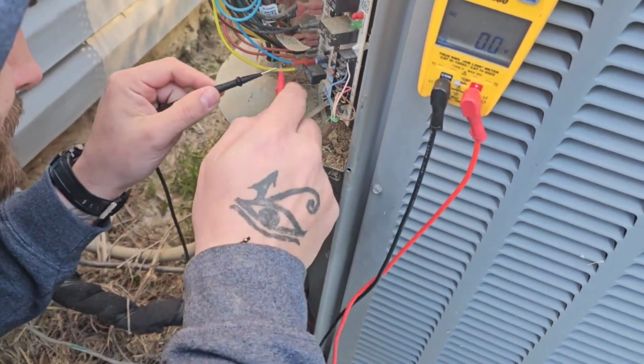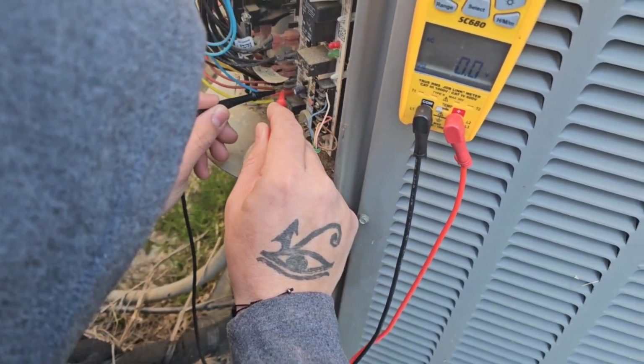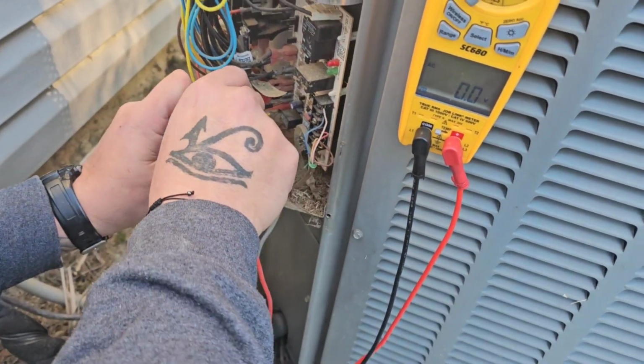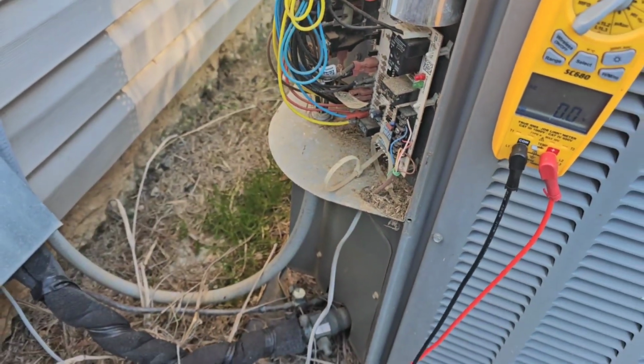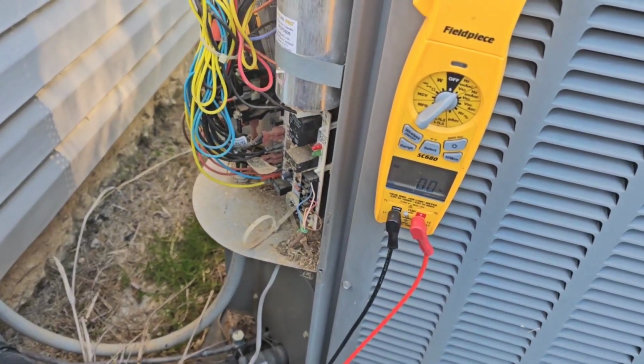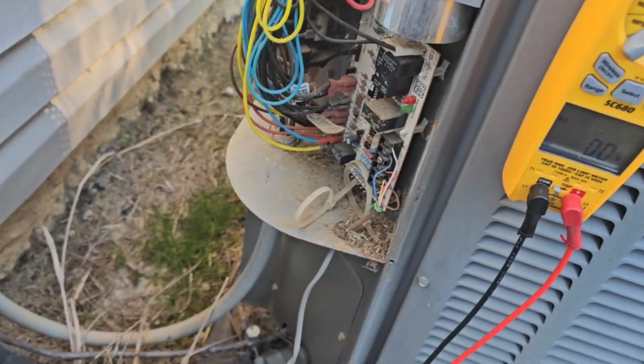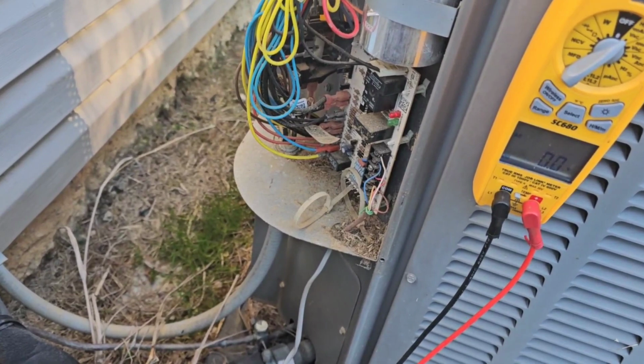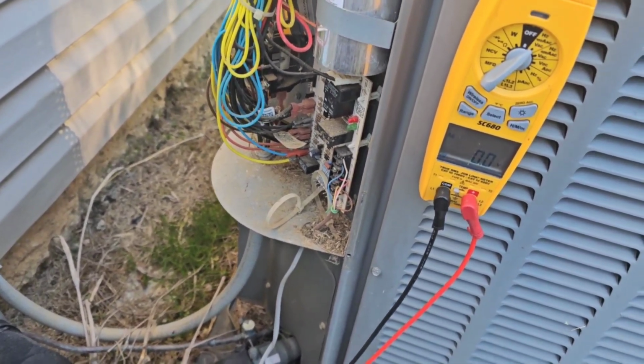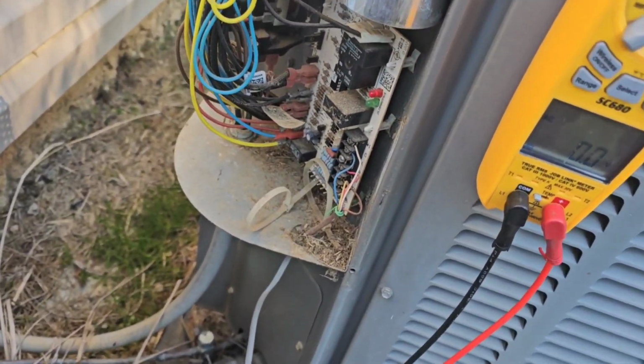So they're on the sides. Yep, but go to the board and check for 24 volts there. Sorry, so still 0. So now this is a normal issue that I come across all the time on these defrost boards. One of those wires is more than likely, or one of those terminals is more than likely not working. So check from one of those wires that you just had.